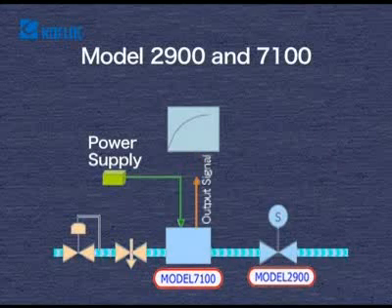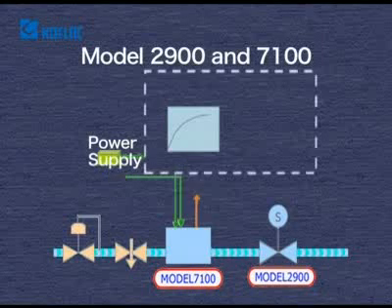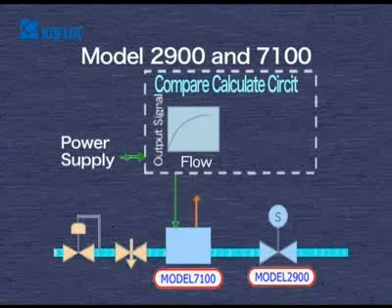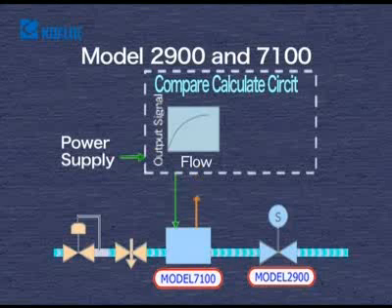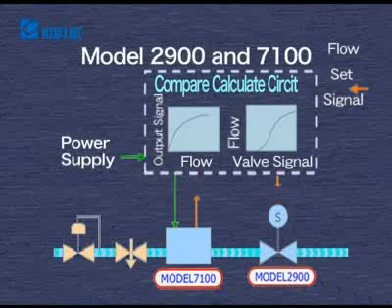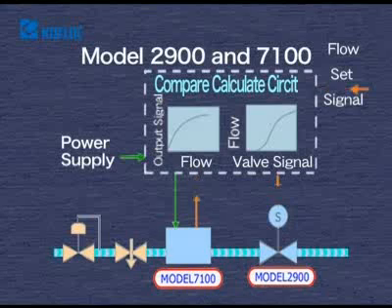Then install a model 2,900 valve in the same gas line. Prepare a comparison operation control circuit separately and input the output signal from model 7,100 sensor to the comparison operation control circuit. Arrange cables to send the flow control signal from the comparison operation control circuit to the model 2,900 valve, and input the flow setting signal to the comparison operation control circuit.